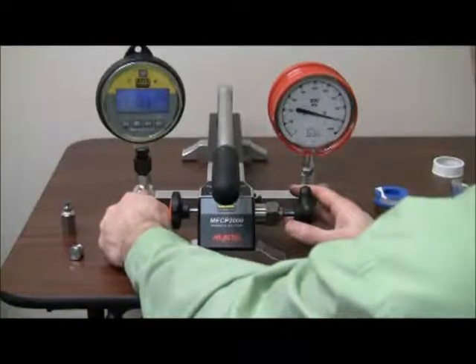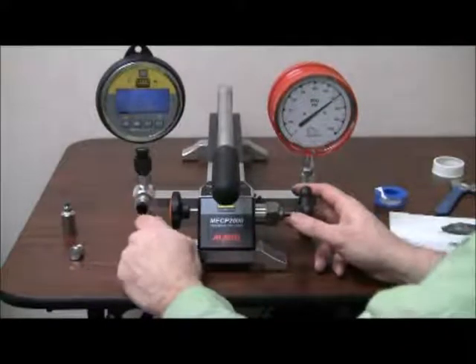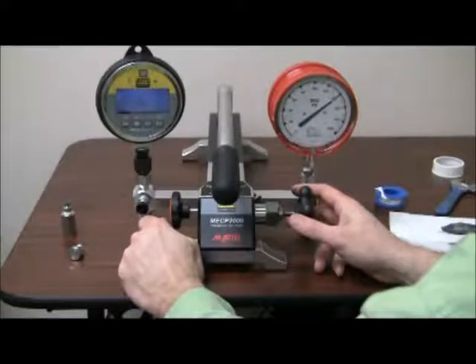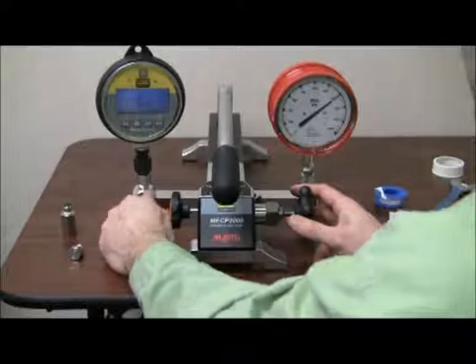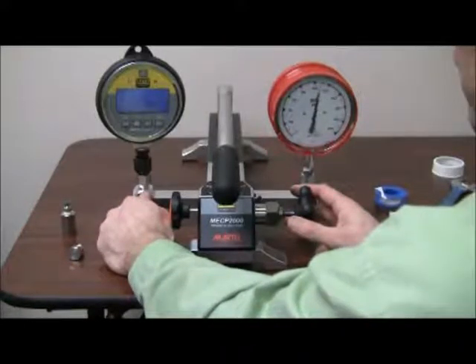Let it settle. We'll bleed off some more pressure here. Use the vernier to increase pressure slightly.